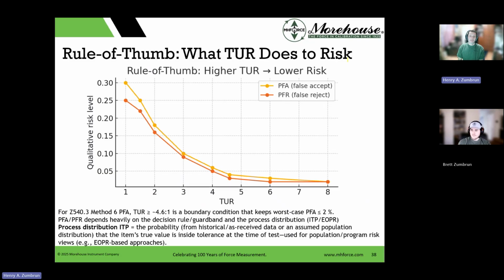When we start looking at what TUR does, it's qualitative. Your exact risk is going to depend on the decision rule, and the only thing I think we can all confidently say is that a lower measurement uncertainty will reduce your overall measurement risk. ITP is in-tolerance probability, and EOPR is end of period reliability. That's historical information. That's basically saying, hey, 95% of the time this passes cal, or 95% of the time Aaron Rodgers hits that throw 40 yards downfield into the bucket. And we can use that information to do both of our curves.